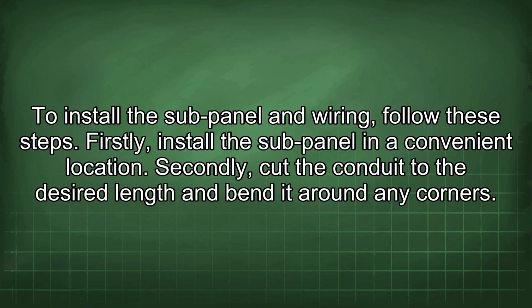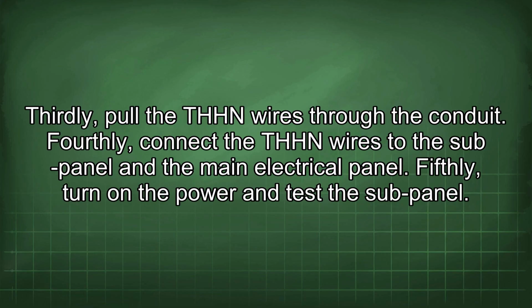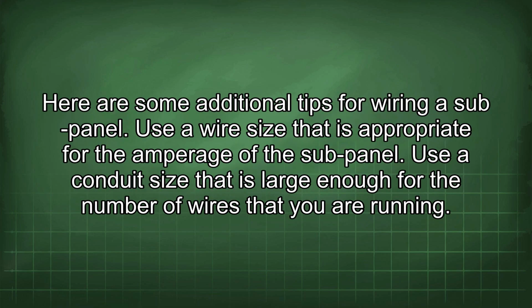Secondly, cut the conduit to the desired length and bend it around any corners. Thirdly, pull the THHN wires through the conduit. Fourthly, connect the THHN wires to the sub-panel and the main electrical panel. Fifthly, turn on the power and test the sub-panel. Here are some additional tips for wiring a sub-panel.